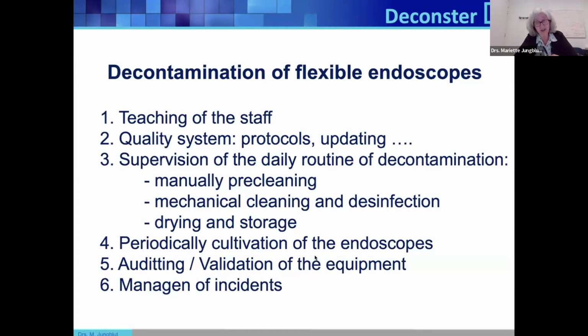Mechanical cleaning and disinfection is, as far as I'm concerned, absolutely necessary after the manual pre-cleaning. And also there, the manual pre-cleaning has to be done immediately after use. Then we have a little time, please, a little, 20 minutes, 30 minutes. And then it has to go into the mechanical cleaning area, as we call it.